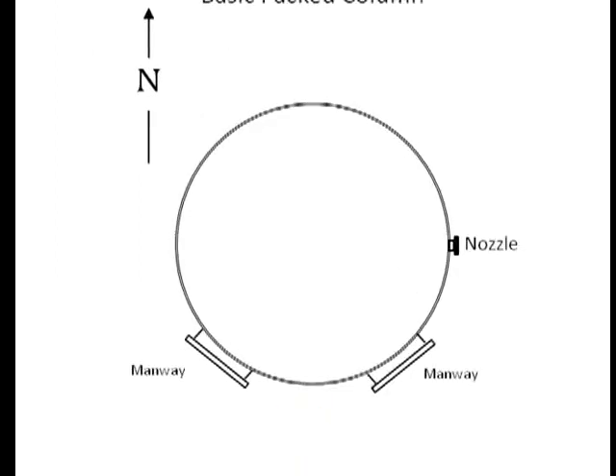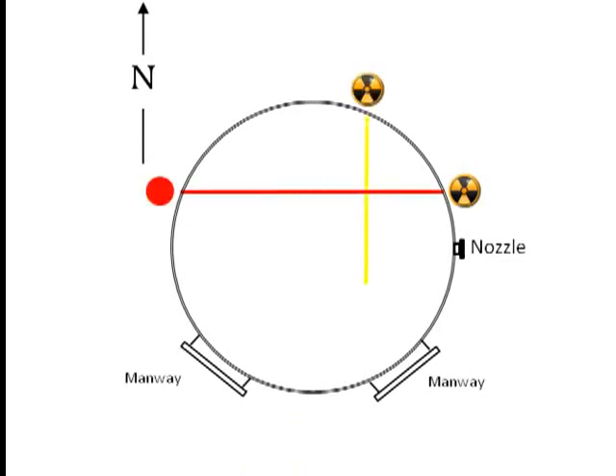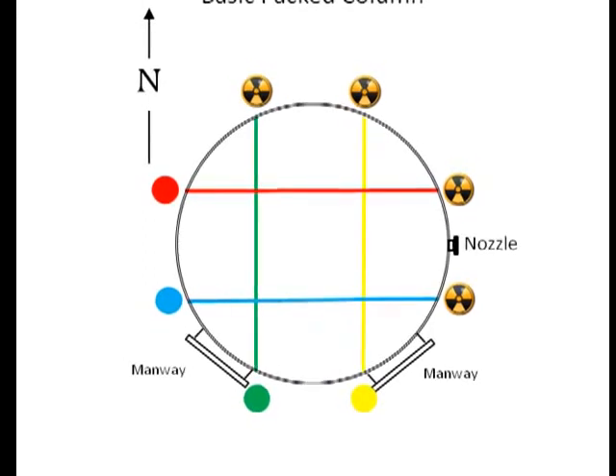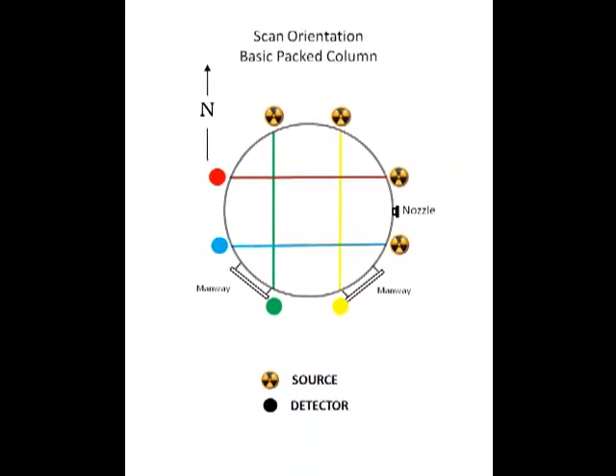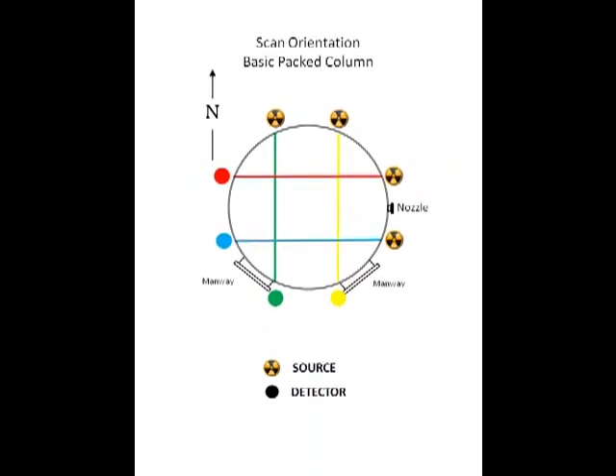As shown in this scan orientation diagram, four consecutive scans were performed, rather than just one, and the results of the four scans are then compared to each other. If the packed sections are operating normally, the four scans should look similar through the packing when overlaid.